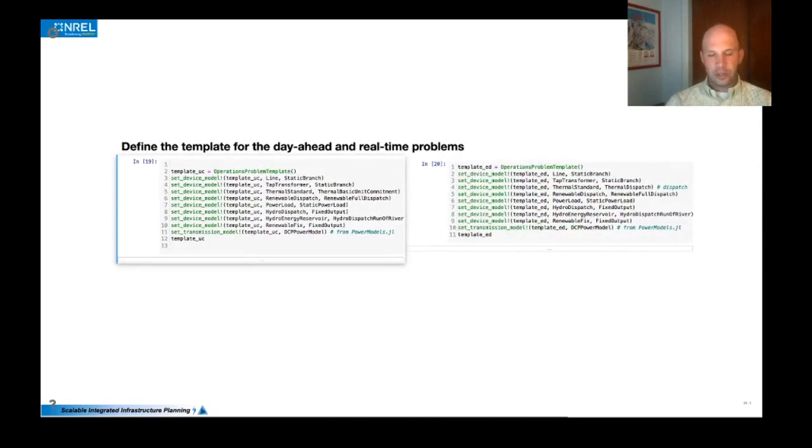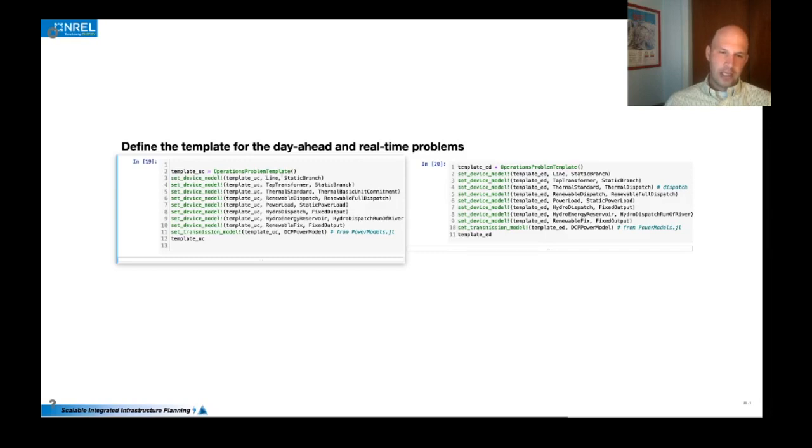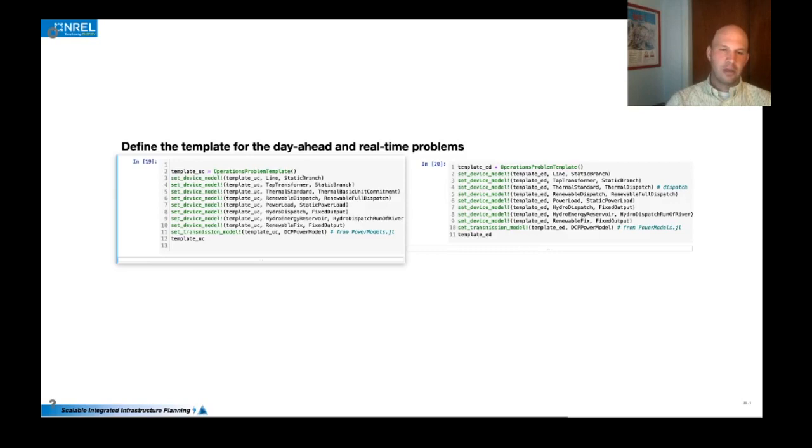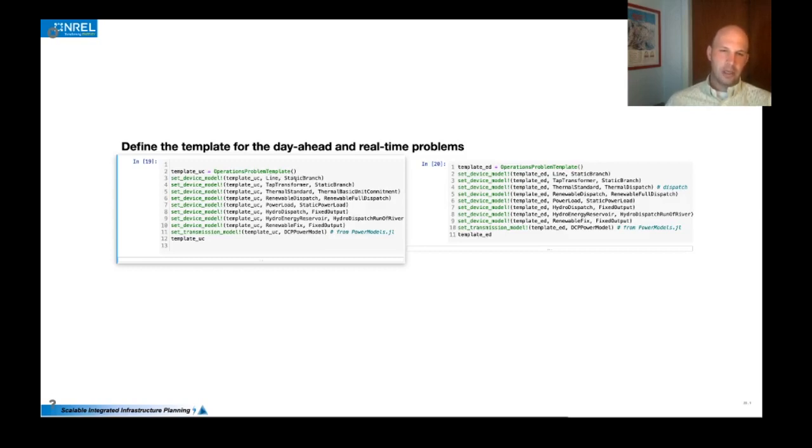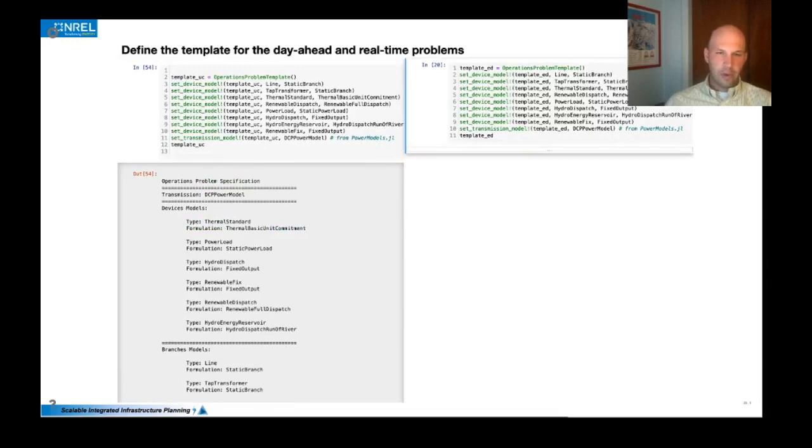And we do that. So starting with the formulation, the way that we specify a formulation is with what we call a template. And we create a template and on the left here, we'll create a unit commitment template. And to do that, for each category of device like lines, we apply a formulation, which is just an abstract type that helps the multiple dispatch navigate the code and apply the correct variables and constraints to each device. So it basically calls the get_components on all the lines and then applies the correct constraint creation and variable creation according to this static branch formulation type. And so you can do that for all the different categories of devices in the system.